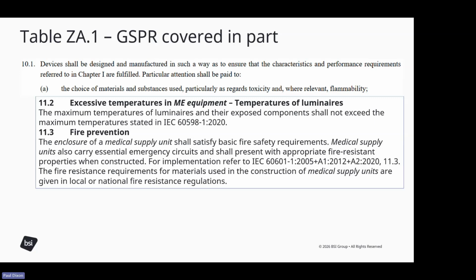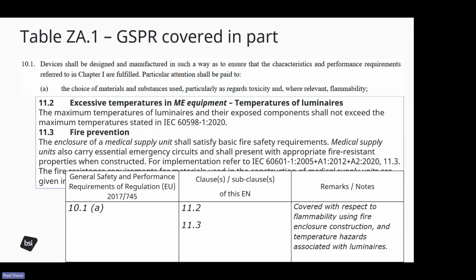In this same standard for medical supply systems, we have a couple of clauses that relate to excess temperatures and fire prevention. Once again, these clauses both have a shall, they are normative requirements, and they cover the temperatures of luminaires and also the fire safety of the enclosure as a whole. So in this case, we included the GSPR 10.1a, we listed both of the two clauses of the standard, and we have a remark that says that it's covered with respect to flammability and the temperature associated with luminaires. It specifically doesn't address the choice of materials and substances as regards toxicity. So the remark demonstrates the scope of the coverage.